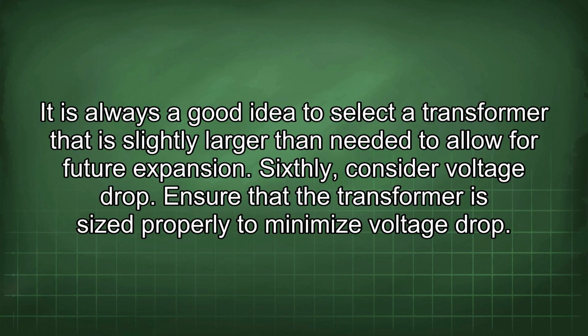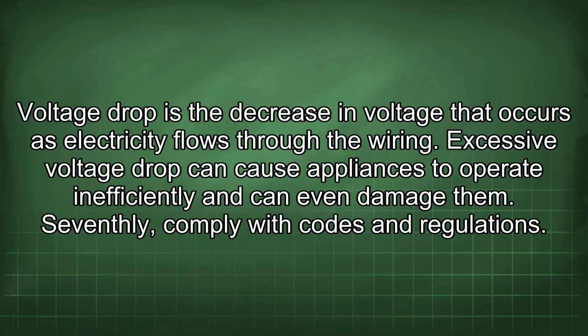Sixthly, consider voltage drop. Ensure that the transformer is sized properly to minimize voltage drop. Voltage drop is the decrease in voltage that occurs as electricity flows through the wiring. Excessive voltage drop can cause appliances to operate inefficiently and can even damage them.